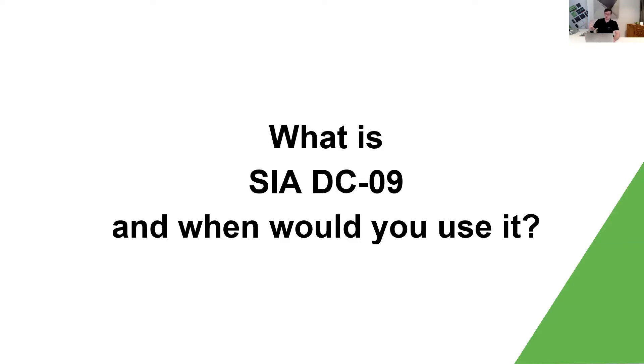We could now have key holder response, and from that introduce things like police response and police monitoring. Then came the idea of wanting to know exactly which detector had gone off - and this is when SIA comes in. SIA and Contact ID, both of which Loxone now supports, allow the sending of actual text to an alarm receiving center. Conventionally on an alarm panel this would still be done through something like a Dualcom module, wired into the speech dialer, ringing through the phone line or a SIM card, passing through Contact ID or SIA data to tell you exactly which zone has gone off.